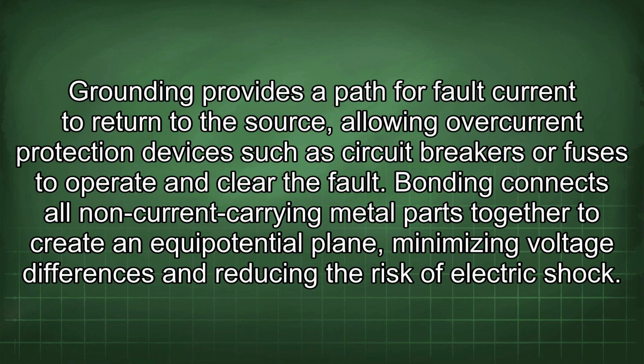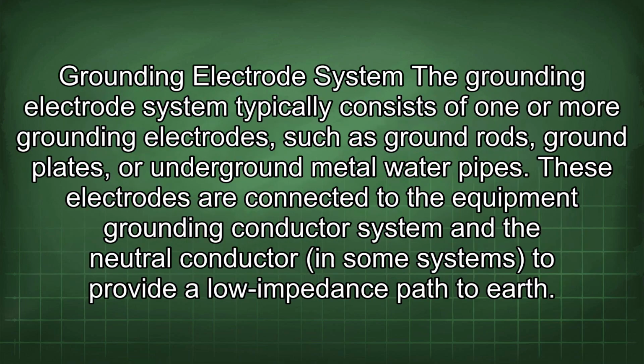Grounding provides a path for fault current to return to the source, allowing overcurrent protection devices such as circuit breakers or fuses to operate and clear the fault. Bonding connects all non-current carrying metal parts together to create an equipotential plane, minimizing voltage differences and reducing the risk of electric shock.